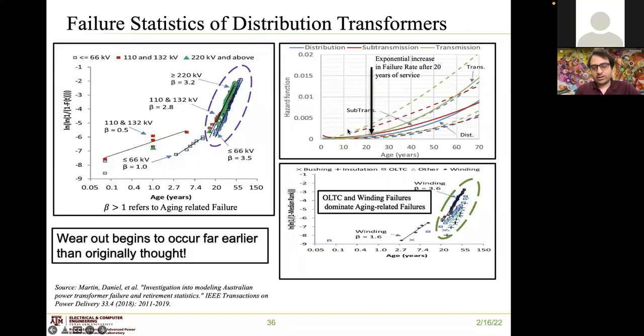This picture on the top right is the hazard function plotted against age. Focusing on the blue curve, the hazard curve for distribution transformers, we see that after about 20 years of age the hazard function experiences an exponential increase, meaning the probability of immediate failure after 20 years increases.